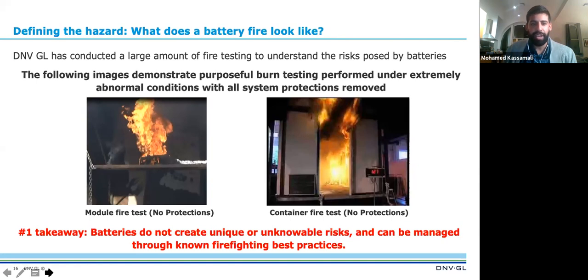The number one takeaway here is batteries do not create unique or unknowable risks and can be managed through firefighting best practices. By that I mean these fires are not that different than a plastics fire. There is a risk of deflagration, but the fire itself can be treated in a similar fashion as other fires are treated, in the sense that copious amounts of water should be used.